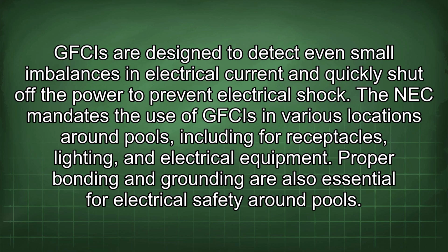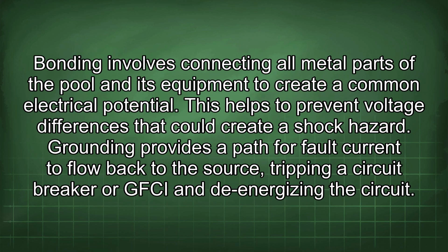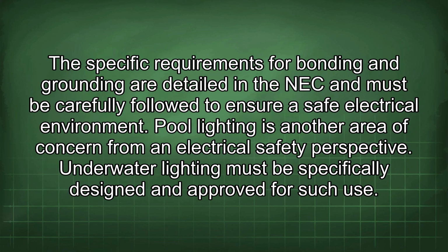Proper bonding and grounding are also essential for electrical safety around pools. Bonding involves connecting all metal parts of the pool and its equipment to create a common electrical potential. This helps to prevent voltage differences that could create a shock hazard. Grounding provides a path for fault current to flow back to the source, tripping a circuit breaker or GFCI and de-energizing the circuit. The specific requirements for bonding and grounding are detailed in the NEC and must be carefully followed to ensure a safe electrical environment.